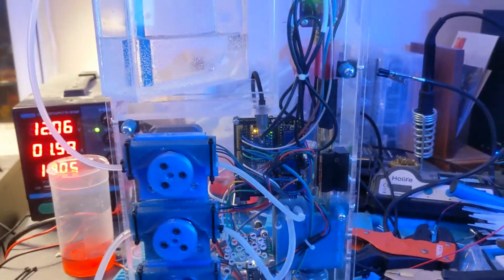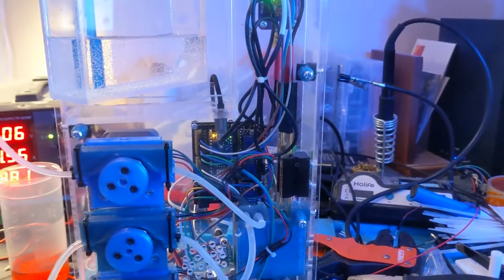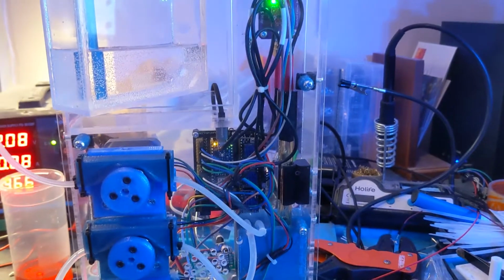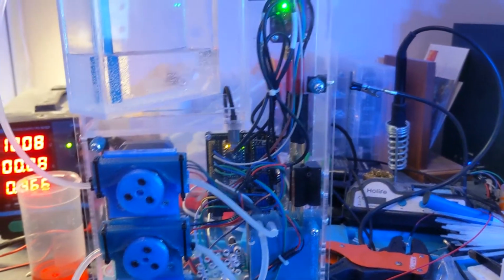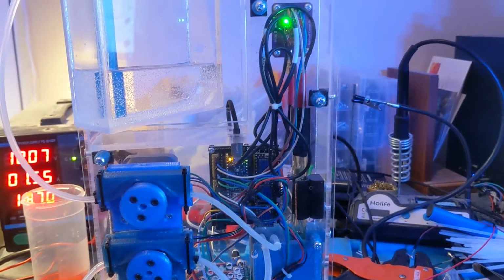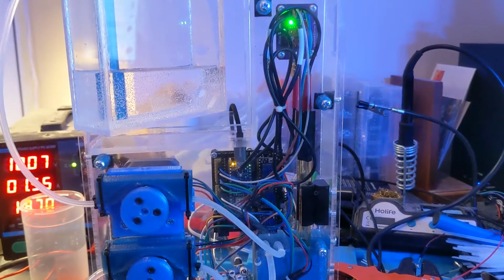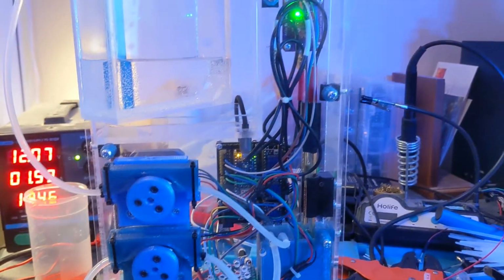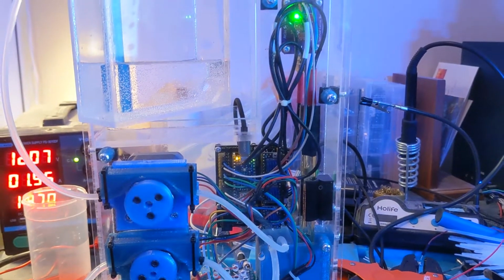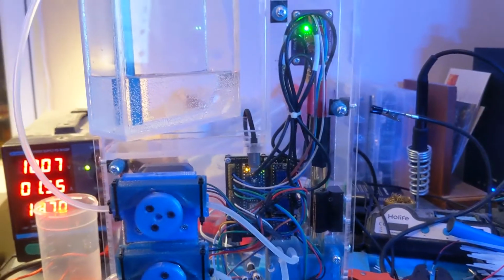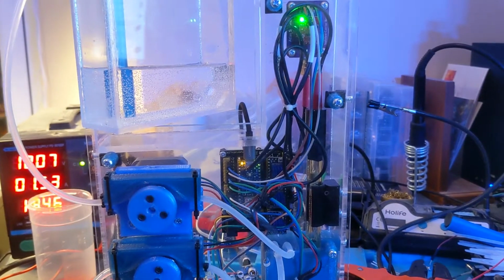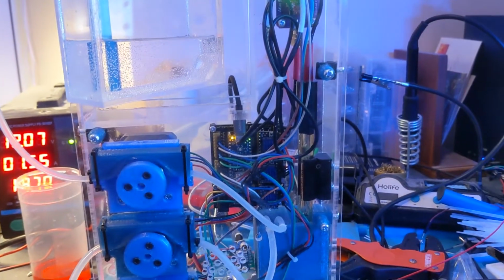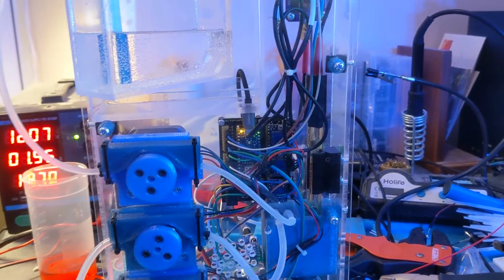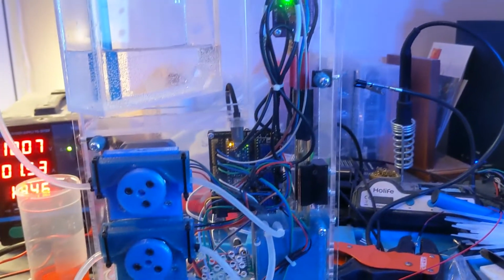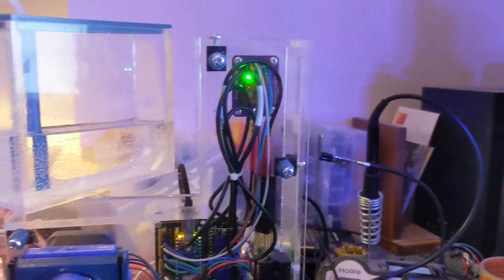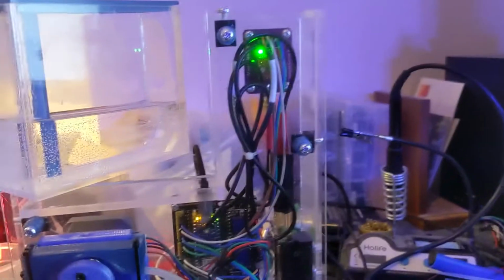So with any alkalinity test, what you're doing is measuring how much of a standard acid you have to add before it reaches a pH of 4.2. And what your handheld, done-by-hand test kits will do is you'll just add the acid manually and add a color change indicator. And so as soon as the color changes, that's your 4.2. Any electronic system is going to use a pH probe like this.